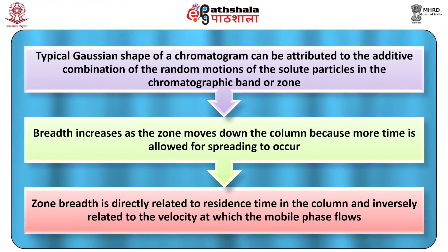The breadth increases as the zone moves down the column because more time is allowed for spreading to occur. Thus, the zone breadth is directly related to residence time in the column and inversely related to the velocity at which the mobile phase flows. Next is standard deviation as a measure of zone breadth. The breadth of a Gaussian curve is of course related to the standard deviation.